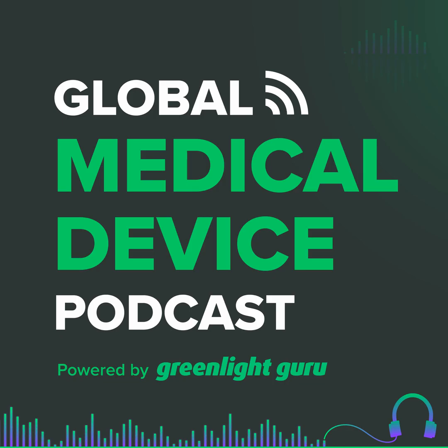But I think with that, if something's going wrong with the device, or even just going wrong with manufacturing and you're having to scrap a bunch of parts and all that stuff, that's when those extra tools are going to be helpful for you, because then you're looking at all those different things. And even if it doesn't lead to patient harm, you have that documented using that other tool. I would keep what's in your regulatory submission to the ISO 14971, those patient harms. I probably wouldn't be putting a bunch of business risks.